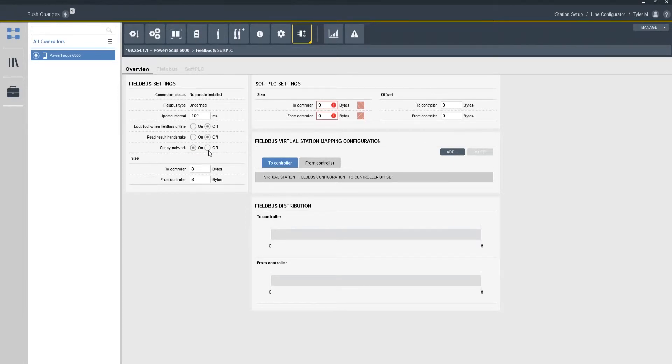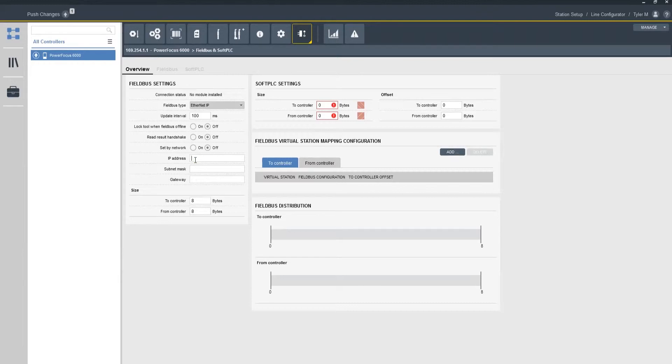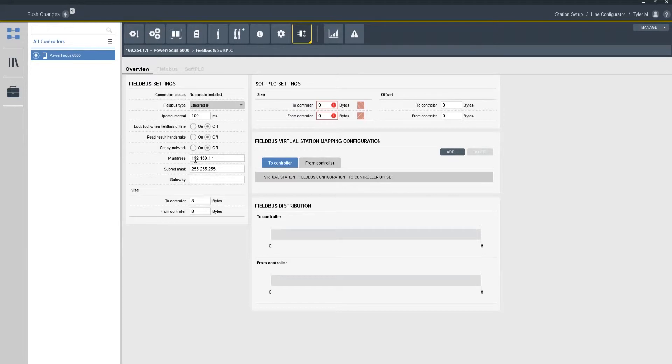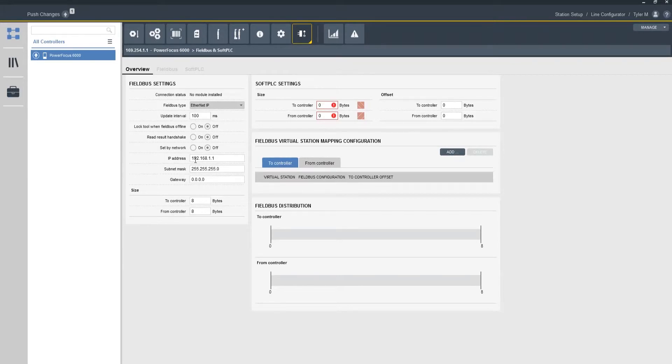But I'm going to leave that set to off and we're going to put in a generic IP address for connection. Now keep in mind even if you do not have a gateway you need to program a gateway in there even if it's 0.0.0.0. So now I've got my generic settings set up for my EIP connection.